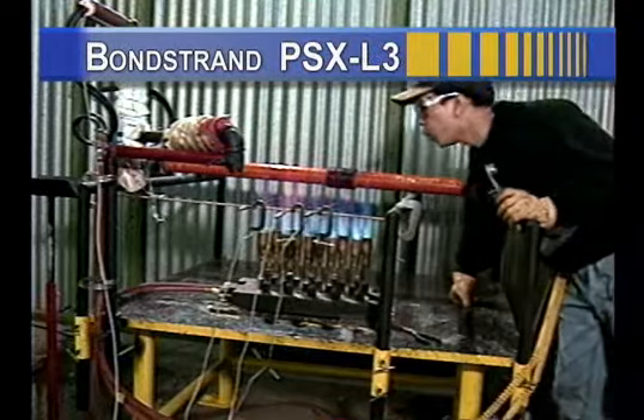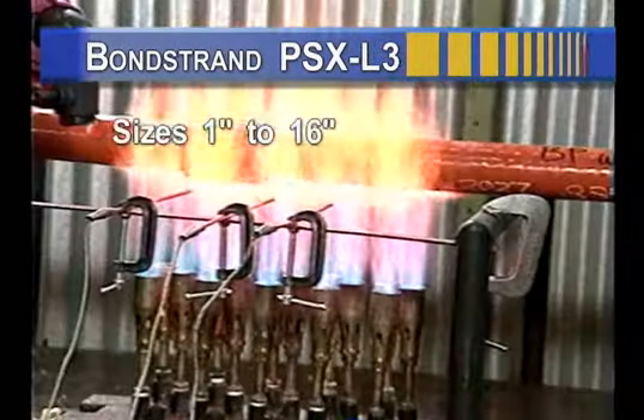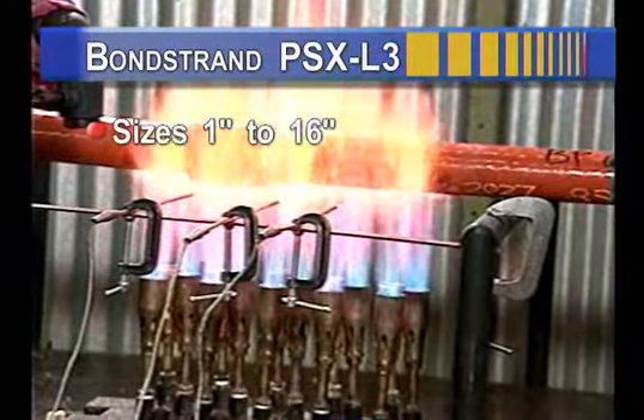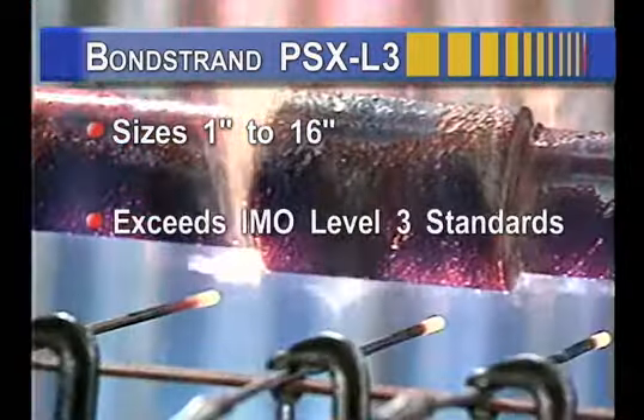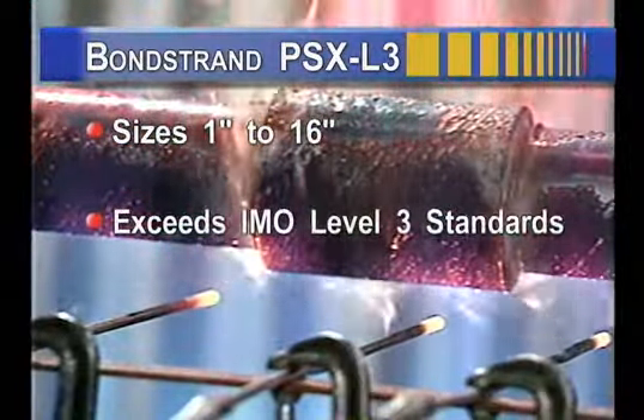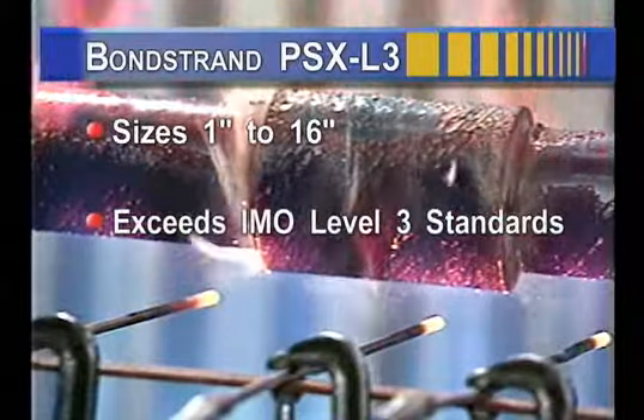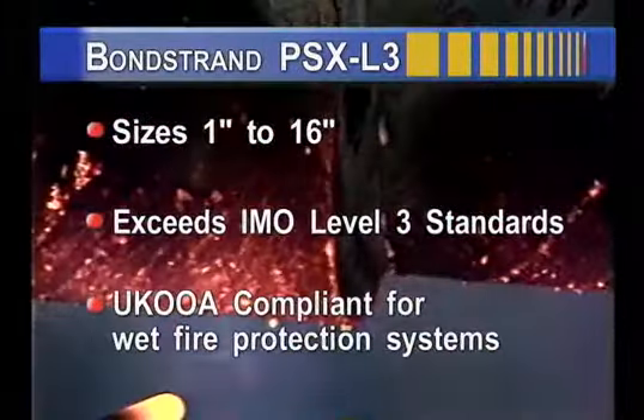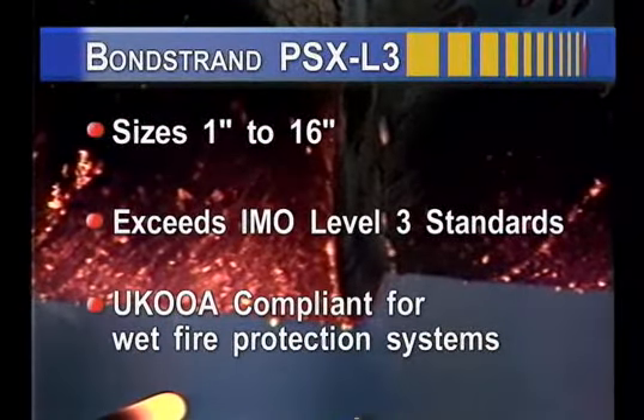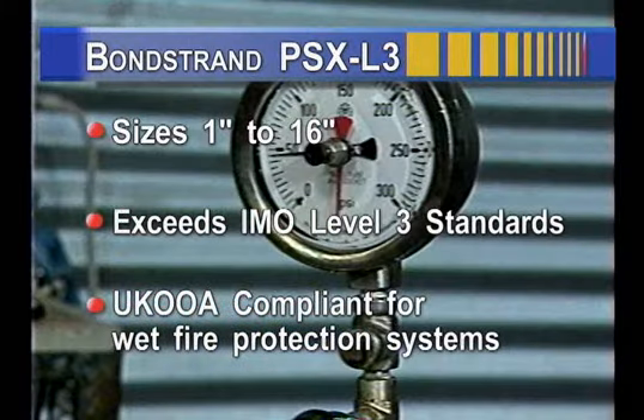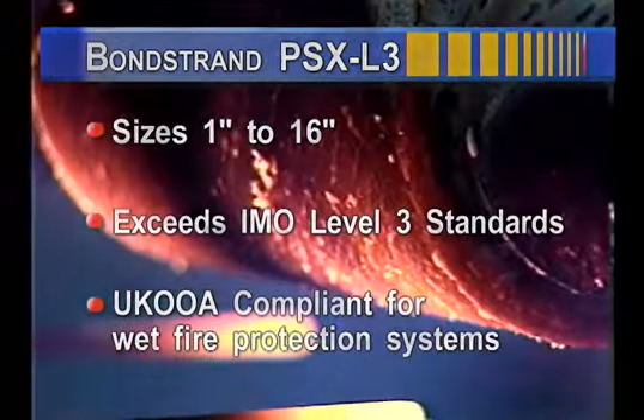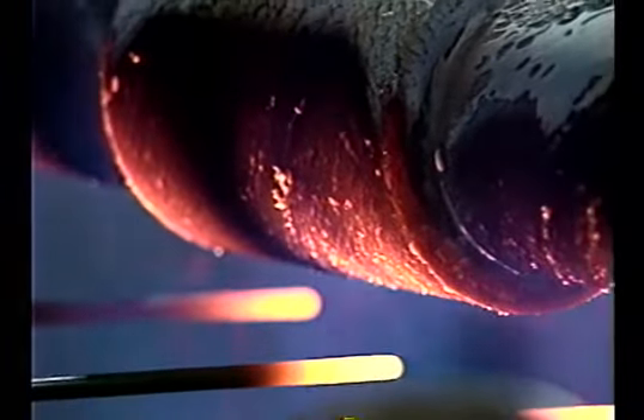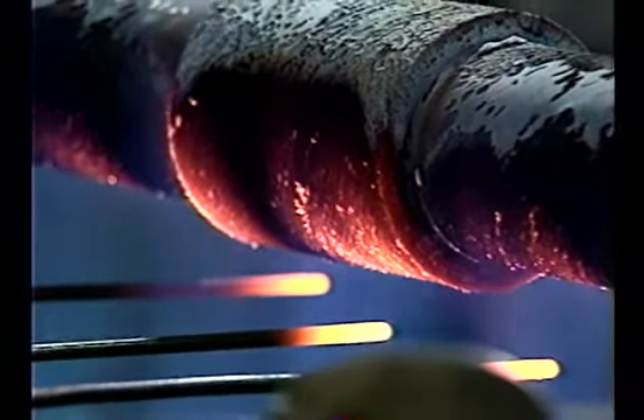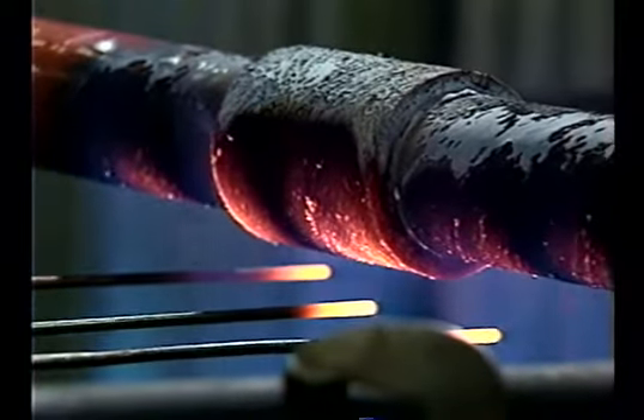Bondstrand PSX L3 is available in sizes from 1 inch to 16 inches. It exceeds the IMO, International Maritime Organization, Fire Endurance Test. Rated to Level 3 and UKOOA compliant for wet fire protection systems, this product is rated from full vacuum to 225 psi. Tested here to 1100 degrees Celsius for a period of 30 minutes, PSX L3 maintains full pressure under even these demanding conditions.